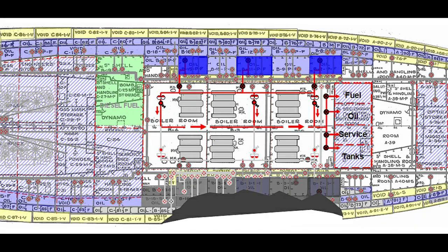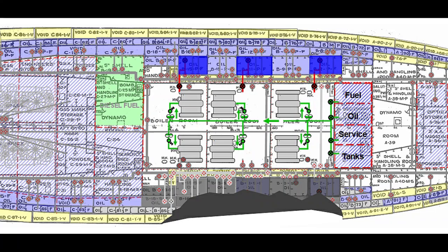Let's now look at the portion of the fuel system that directly serves the boilers. When we do that, it becomes apparent that the service tanks actually serve 2 purposes. They store fuel that is kept hot so that it will smoothly flow through the service pumps, a final heater stage, into the boilers. More importantly for damage control, they also serve as buffers that can provide fuel without being replenished long enough to change tanks or solve most fuel quality or feed problems.